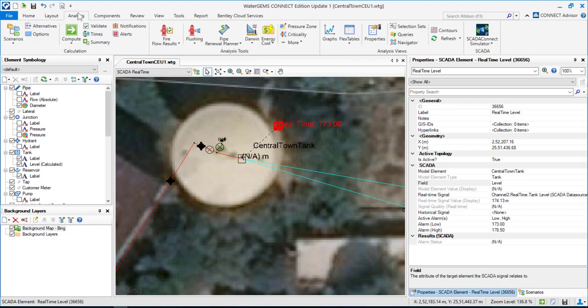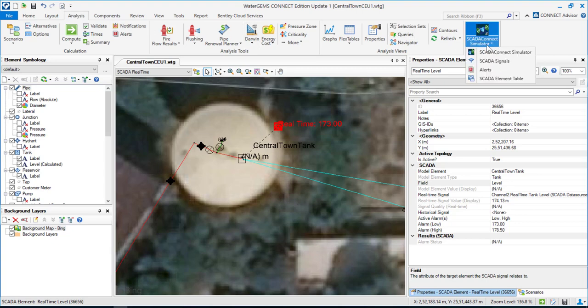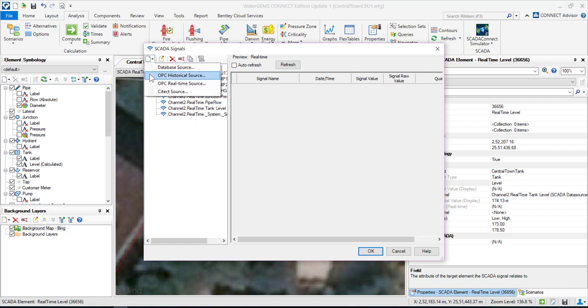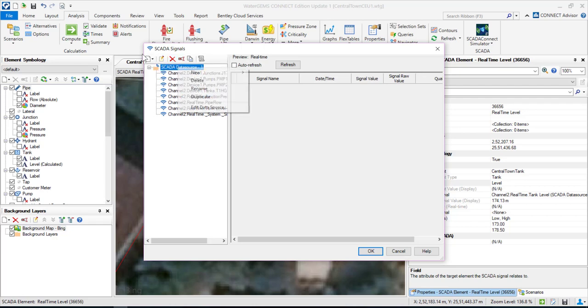Next comes importing the SCADA data and associating it to these SCADA elements. Under SCADA Connect Simulator, you have a tool called SCADA Signals. You can set up these signals from different data sources — it can be a database file, an OPC historical source, an OPC real-time source, or a SCADA server from which you can directly import SCADA data. In our case, it is a real-time source coming from a live server.